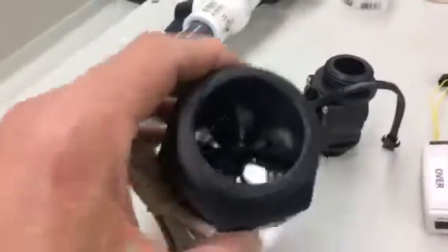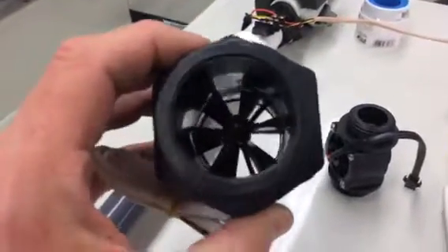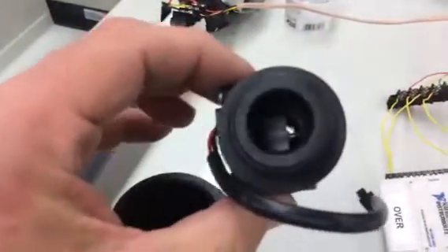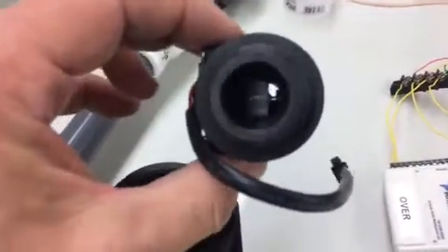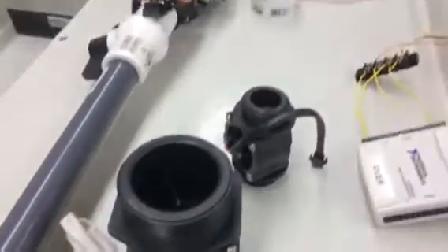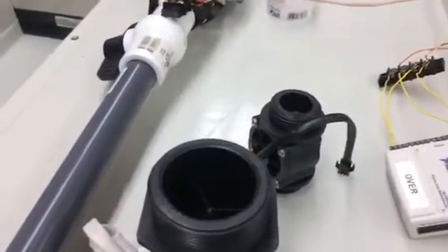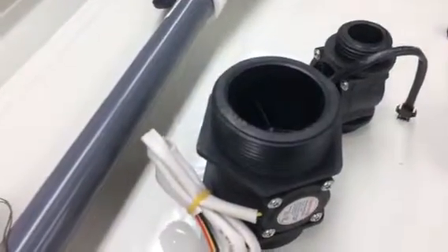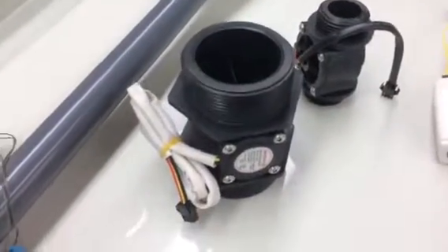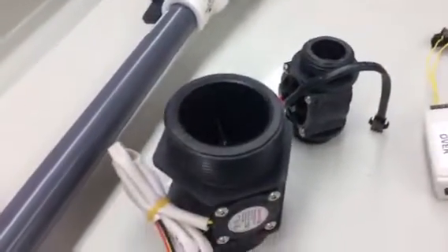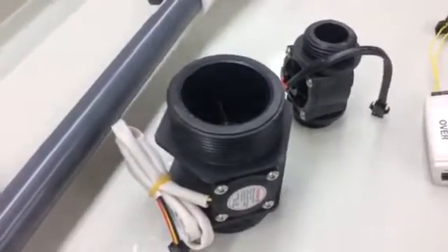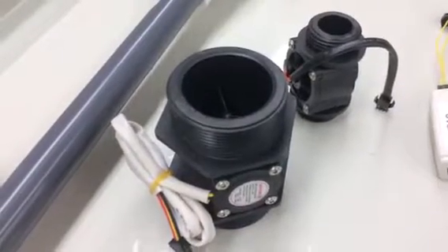These have either a turbine inside, you can see the turbine in there that's going to spin, or a paddle wheel. It's pretty hard to see the paddle in there, maybe you can see it. They operate a Hall effect sensor, which is a switch, and the result of the switch and the turning turbine is going to be a square wave. If we can get the frequency of the square wave, we can get a relationship to how much fluid is going. So there's a direct relationship between the hertz of the pulse coming from the sensor and the flow rate.